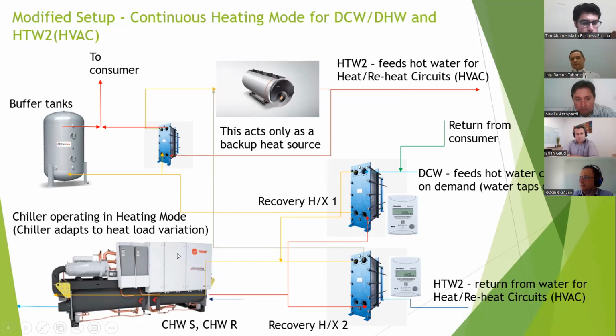Now we have the chiller that can go up to 68 degrees, which means I can heat all my hot water. I can supply all my hot water demand, and I can still take care of my HVAC hot water demand as well. The first thing I installed was energy meters. We have two physical energy meters here that give me the instantaneous power output and the total accumulated energy recovered. So where does the boiler come into play now?